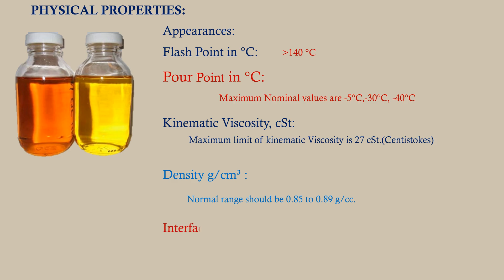Interfacial tension in Newton per meter: interfacial tension refers to the molecular attractive force between the unlike molecules of oil and water. It is measured in Newton per meter and indicates the deterioration of transformer oil. Soluble contaminations in the oil decrease the interfacial tension values.